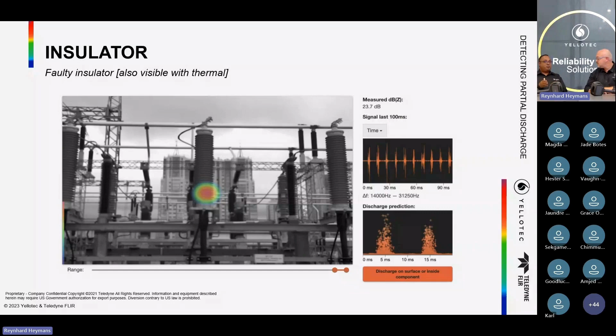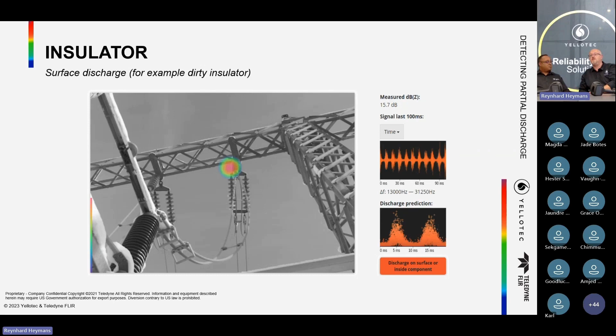Again, here we've got some high voltage corona discharge. Now, please bear in mind, not all discharge is disruptive or destructive. Here you can see this is a discharge into air. So that's not particularly dangerous at that point in time. Okay. And here we go again, more examples. You've got insulators, dirty insulators. What happens? It starts to create a surface discharge, and this could be dangerous. I mean, surface discharge can cause a meltdown in the substation, and then you've got areas without power and breakdown again, and the cost of breakdown is obviously really expensive. And a nice thing about it is all of this is done from ground level. Exactly, it's all done from distance.